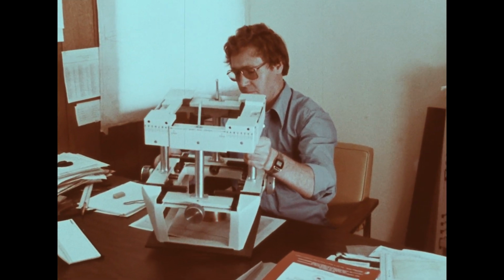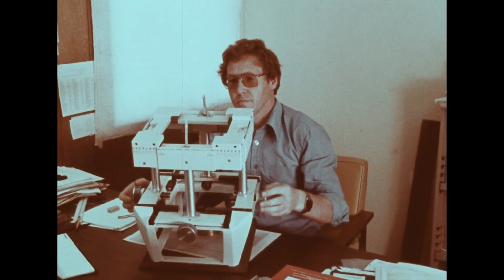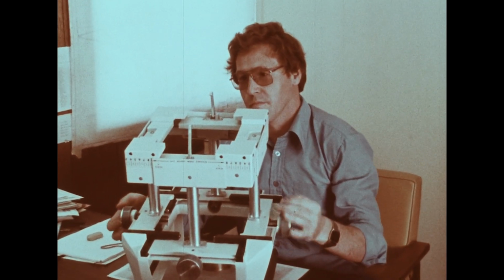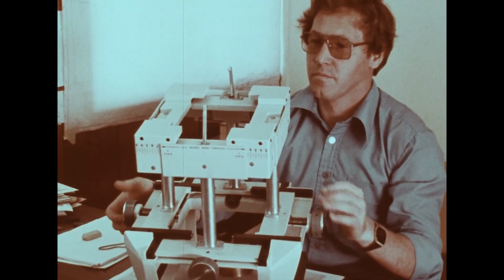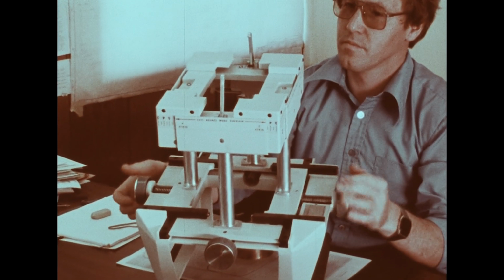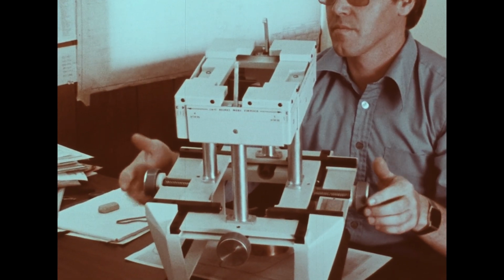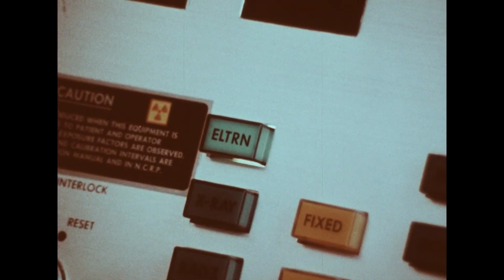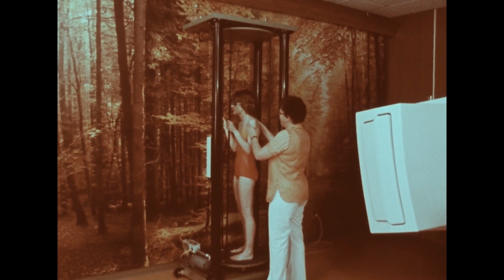This same double-foil system has made it possible to design a lightweight variable electron collimator for square and rectangular fields between 6 by 6 centimeters and 20 by 20 centimeters. When electron is pressed, the target, flattening filter, and photon dosimetry assembly will automatically slide out of the beam path, and the double foil, along with the electron dosimetry assembly, will slide in.